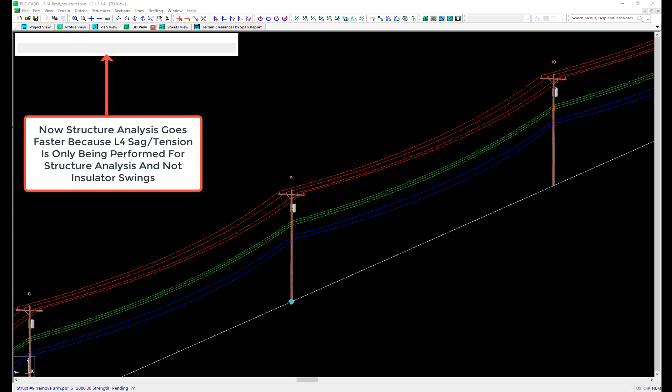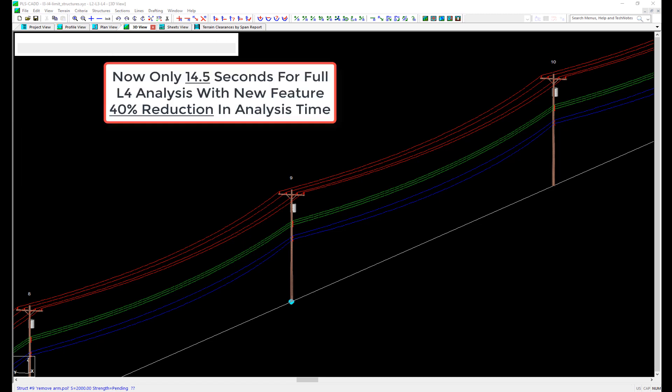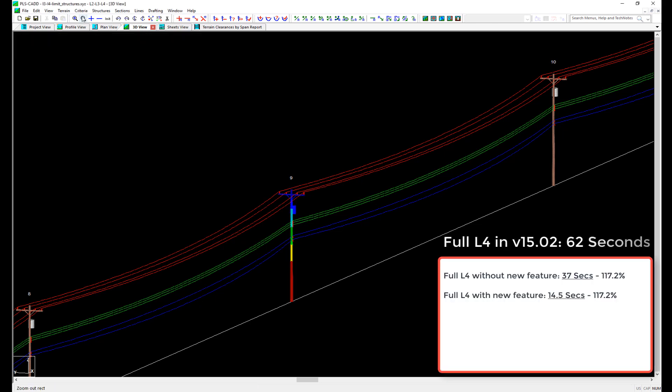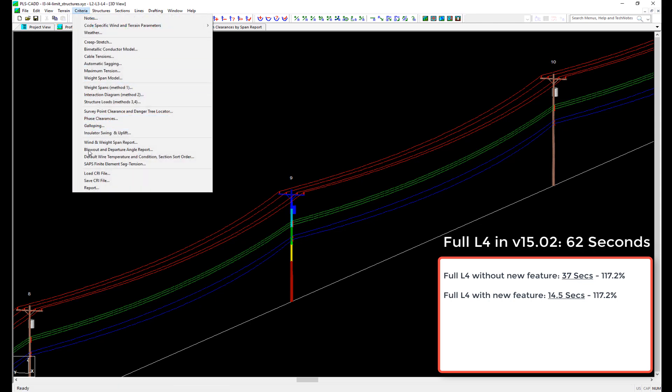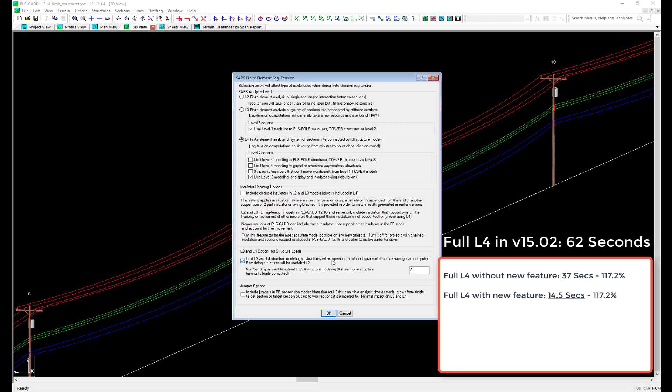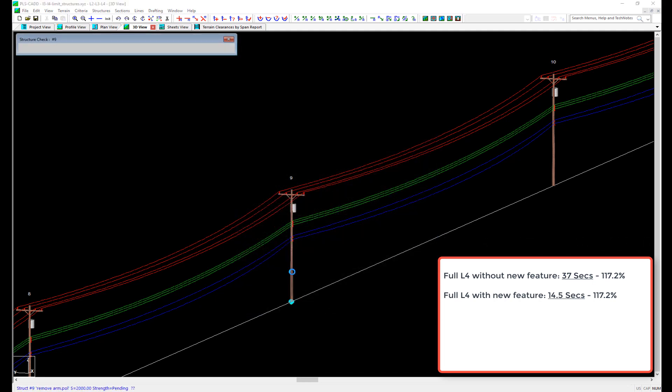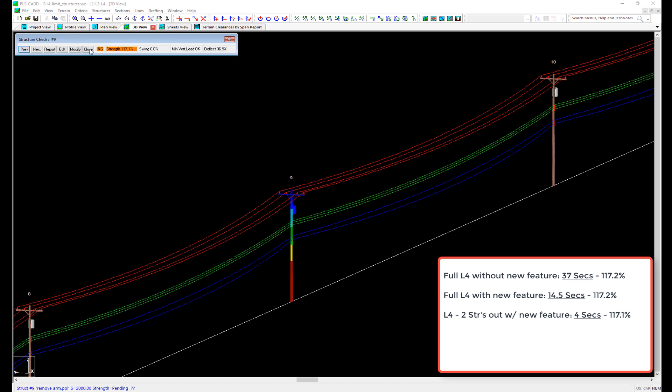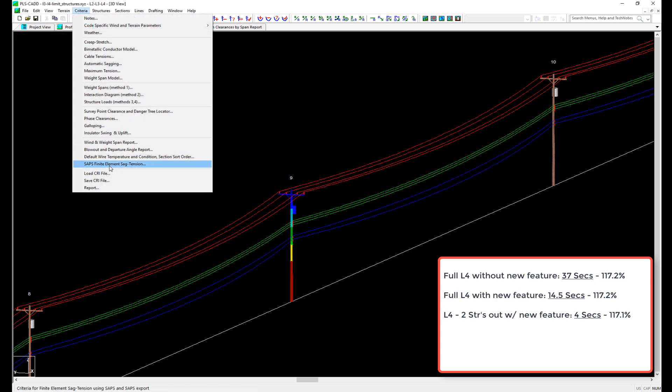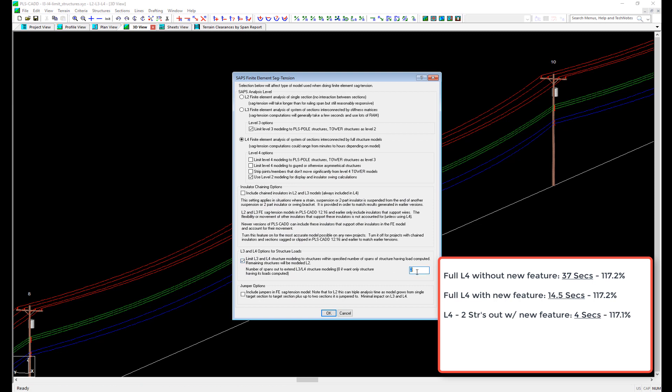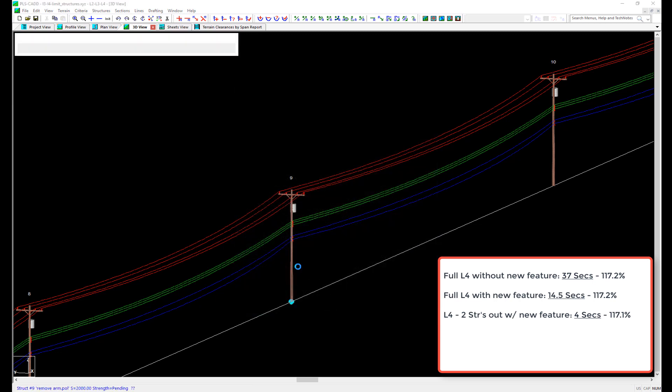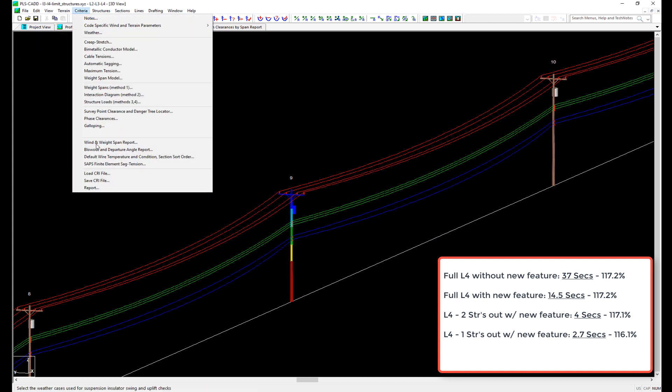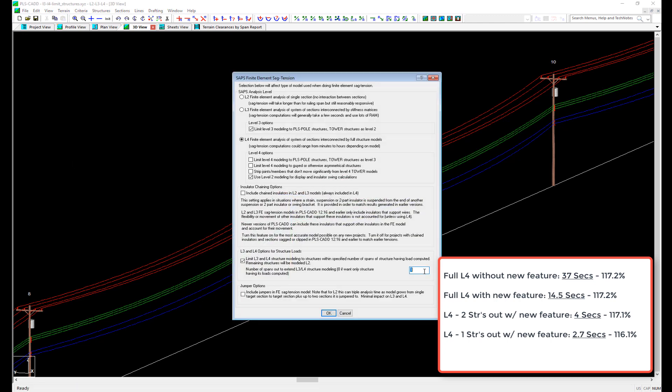So we can see that for a full L4 analysis, the structure utilization is 117.2%. In comparison to a L4 analysis where we look at only two, one, or zero structures beyond the one being checked, we can see we have utilizations of 117.1%, 116.1%, and 102.3%, respectively. Notice how the analysis times get faster and faster when we enter less structures beyond the one we're checking to be included in the analysis. And for this example, we only need to go one structure beyond the one being checked to get results almost identical to the full L4 sag tension analysis.